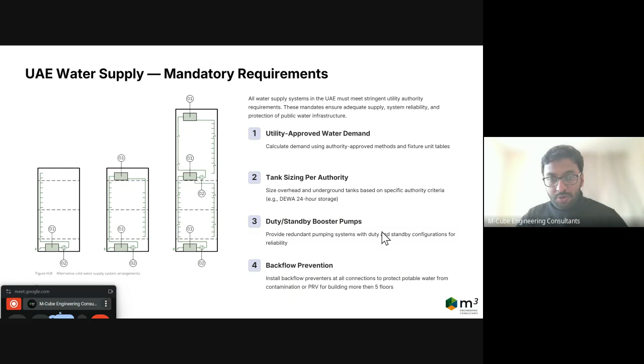Tank size must be as per the authority. DEWA specifies 24-hour storage for the underground tank, and the overhead tank can be equal to or half of the underground tank. The same applies in SEWA and other authorities. Ensure you show standby or booster pumps on the roof, and backflow prevention valves or PRVs for super high-rise buildings. For example, in a G+50 building, you need proper pressure breakers and PRVs to avoid excess pressure within the pipes. These are mandatory requirements to look out for when submitting drawings to the authority.